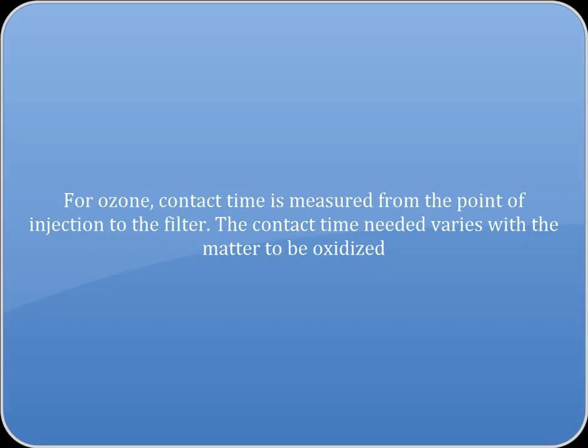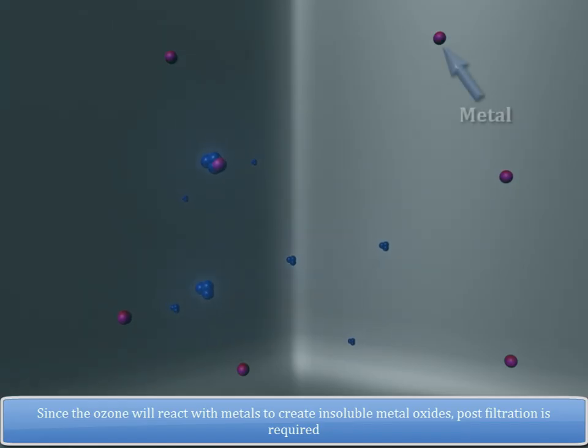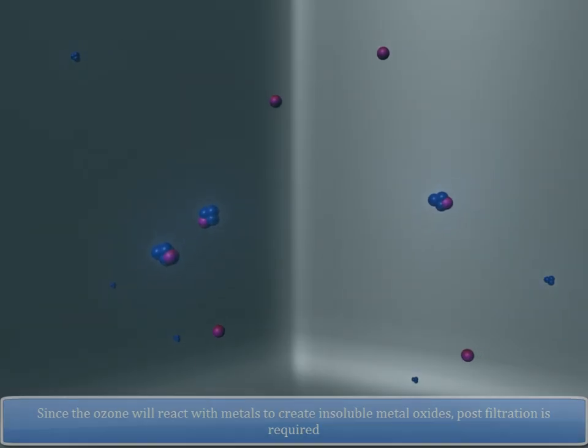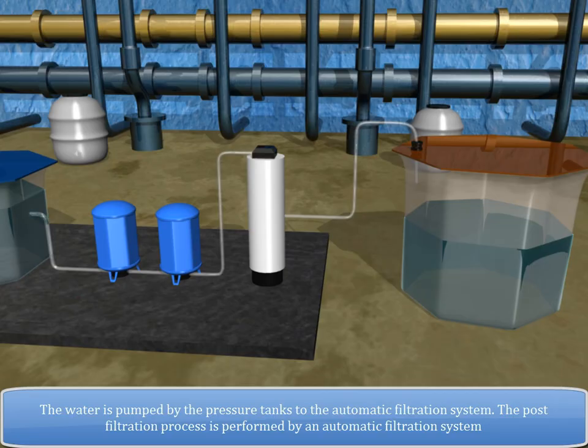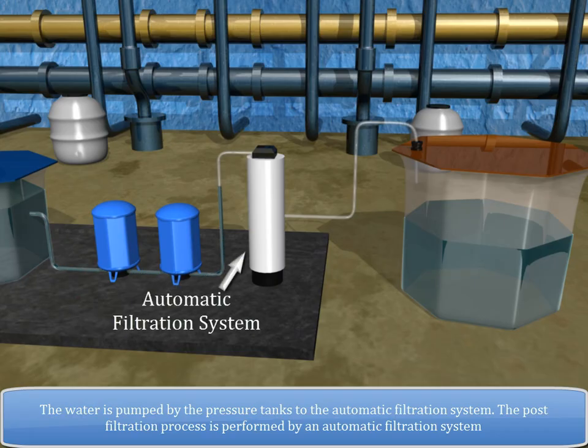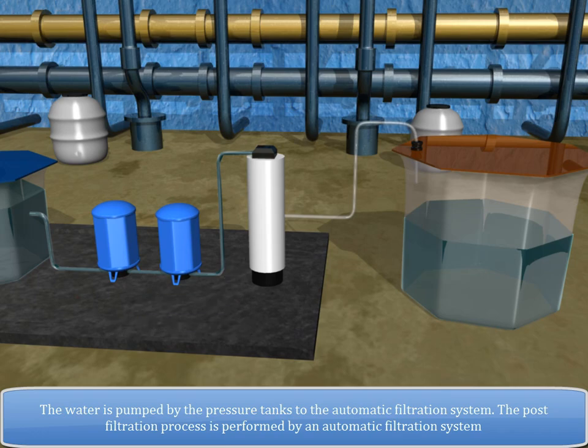The contact time needed varies with the matter to be oxidized. Since the ozone will react with the metals to create insoluble metal oxides, post-filtration is required. The water is pumped by the pressure tanks to the automatic filtration system. The post-filtration process is performed by an automatic filtration system.